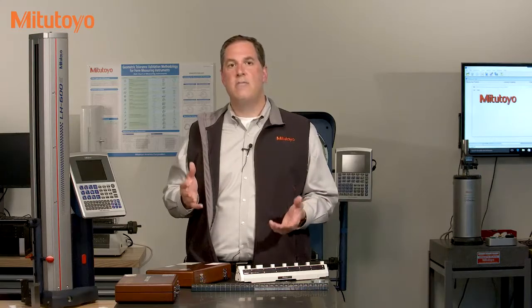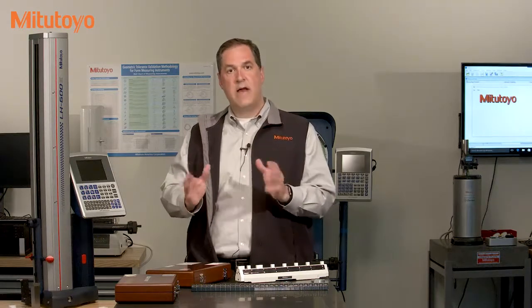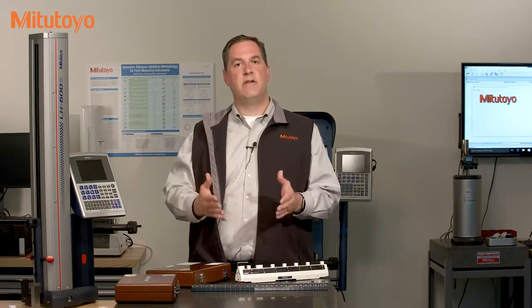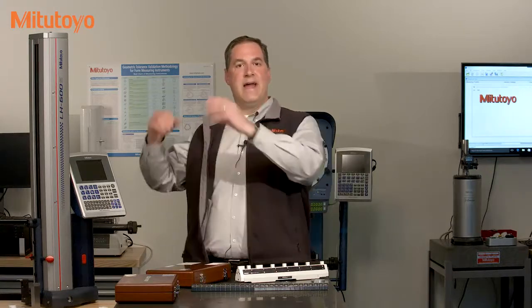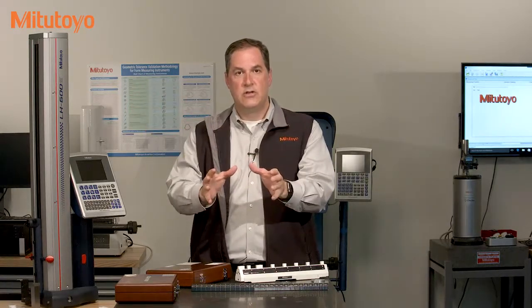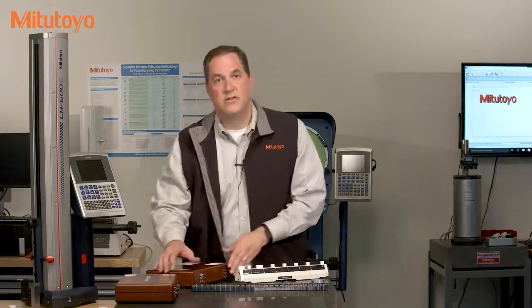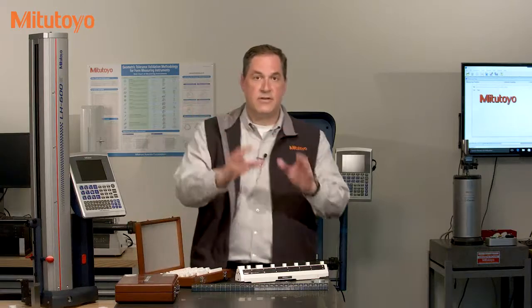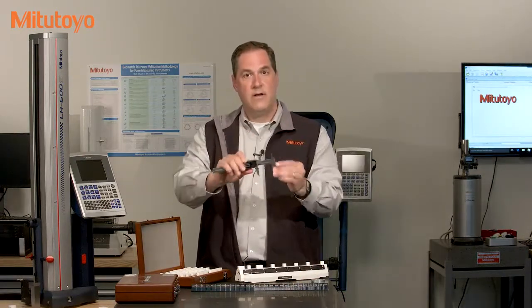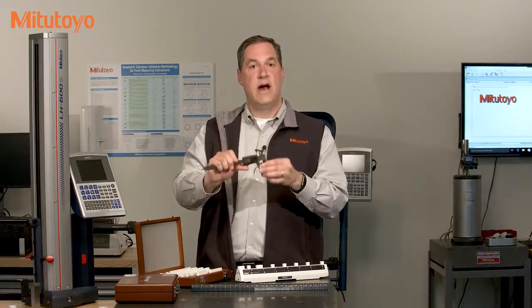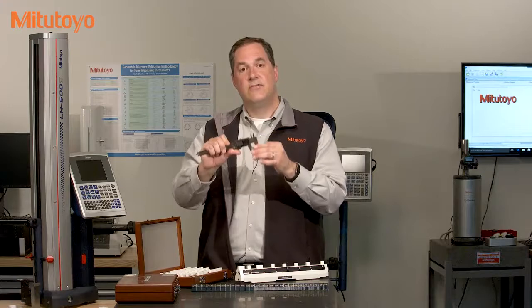In the end, our master gauge blocks are actually used very infrequently, which allows us to absorb the NIST turnaround time and also helps preserve our masters for decades of use. At NIST, our master blocks are then compared to their masters, which are in turn compared to laser systems which are directly linked to the realization of the meter at NIST. So it goes from NIST masters to their gauge blocks, to our masters, to our working masters, to the local lab's masters, to the customer's caliper checker, to the customer's caliper, to the parts being measured on the shop floor. And that's traceability.